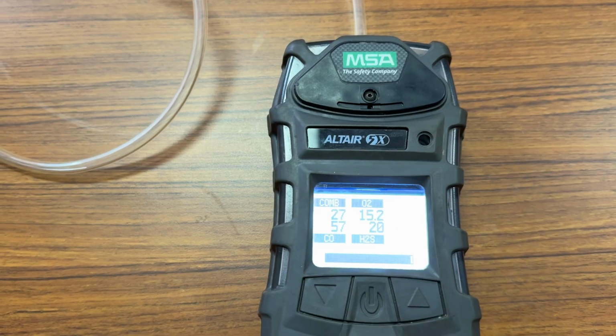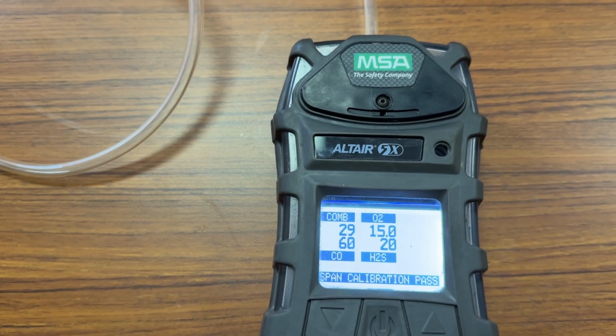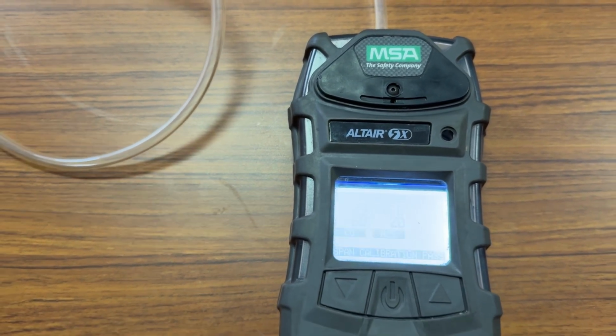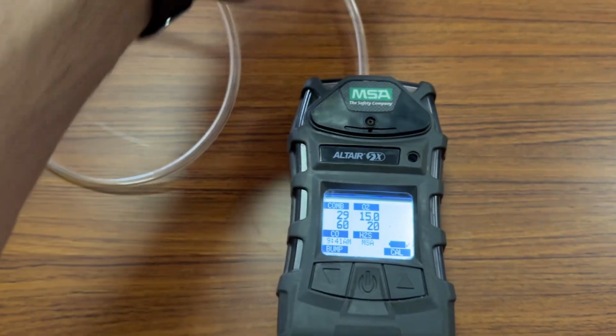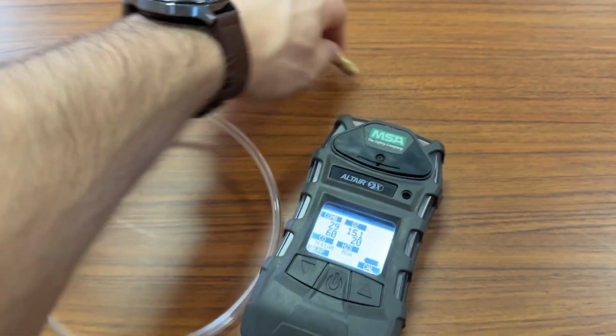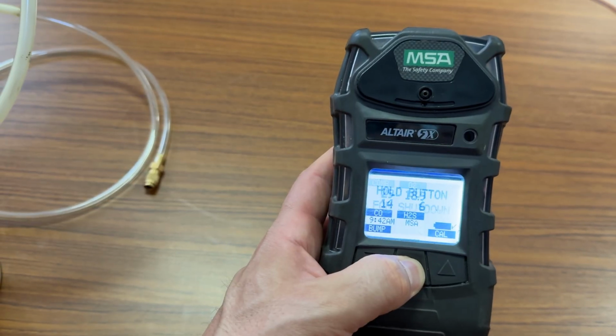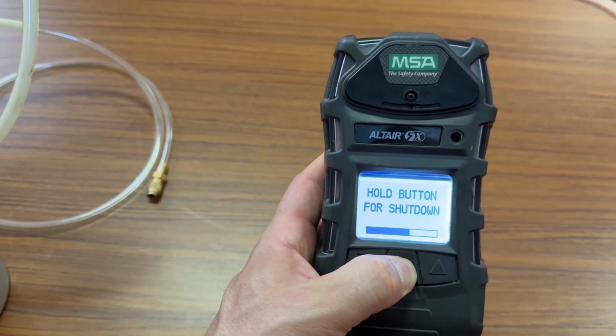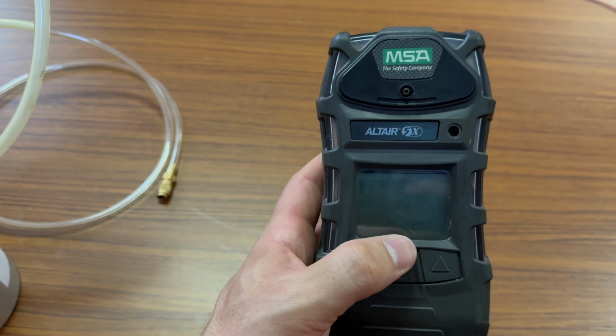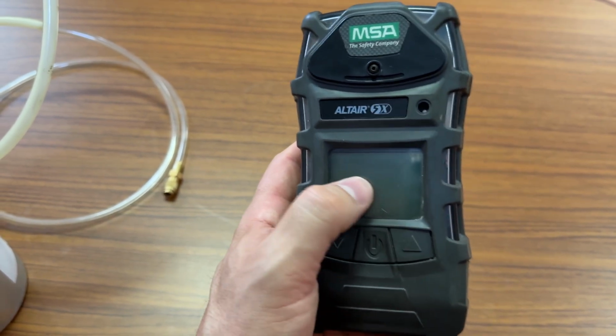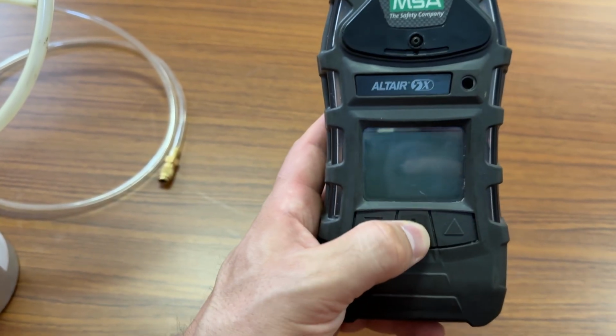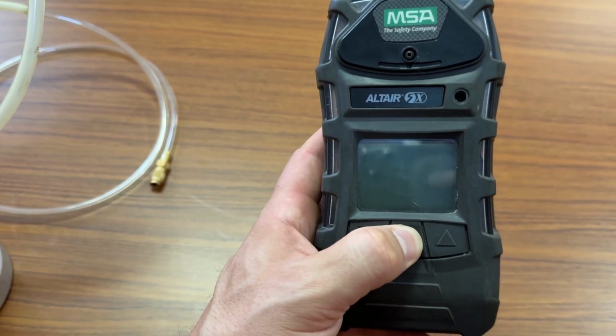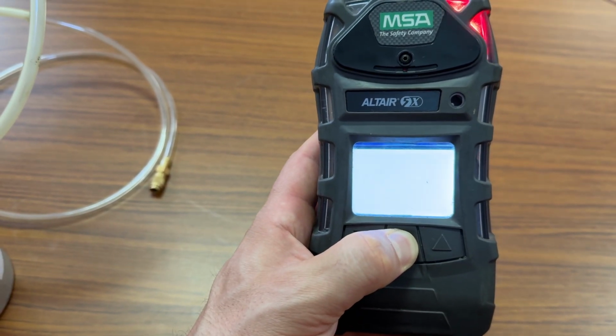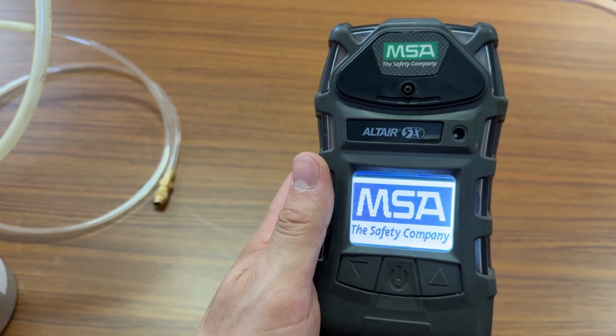A little bit remains. Okay, span calibration pass. Very good. And now we can disconnect this pipe and restart. Just hold on this button. We will restart and see the date of calibration should be updated. Okay, let's start again. Hold on the button. It will ask again for pump test.